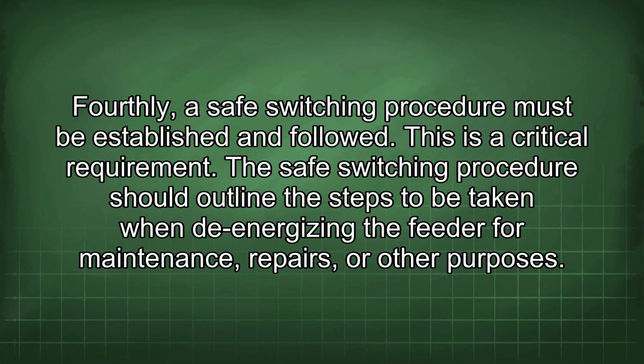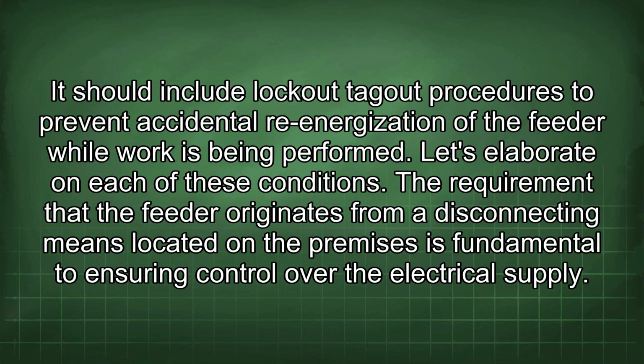Fourthly, a safe switching procedure must be established and followed. This is a critical requirement. The safe switching procedure should outline the steps to be taken when de-energizing the feeder for maintenance, repairs, or other purposes. It should include lockout-tagout procedures to prevent accidental re-energization of the feeder while work is being performed. Let's elaborate on each of these conditions.